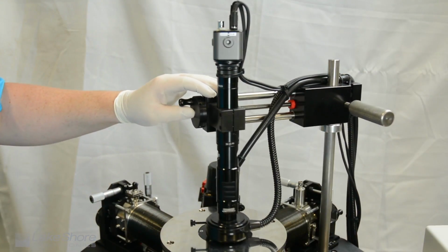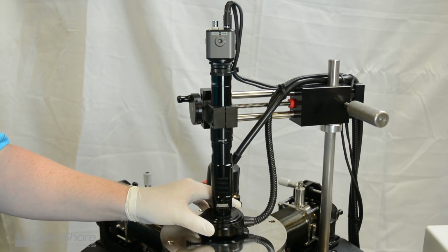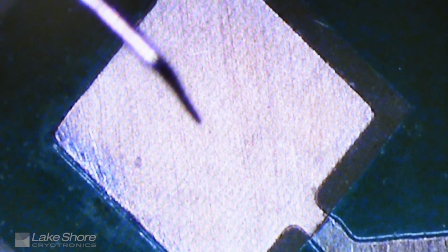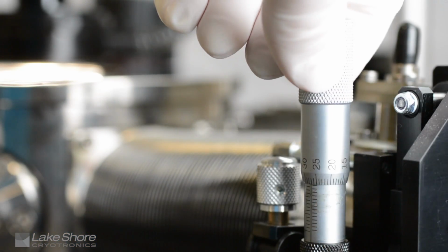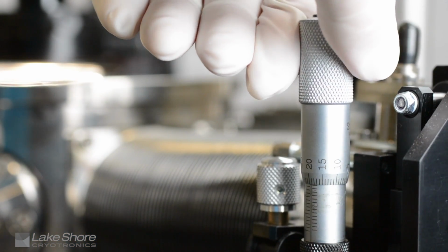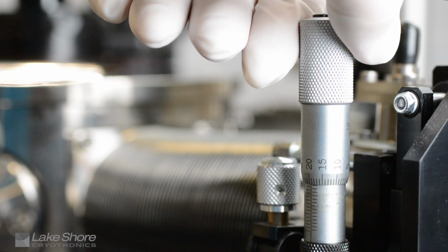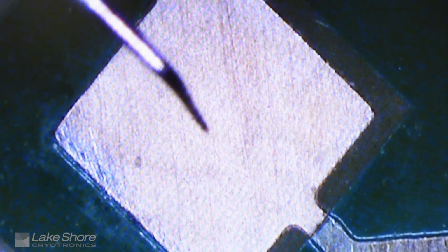Then we will swing the microscope back over the viewport and adjust the microscope to fill the monitor with the sample image and focus at the height of the sample landing pad. Use the Z-axis micrometer or Z-axis adjustment to lower the probe tip until the tip begins to come into focus. When the tip begins to come into focus, begin to slow the downward adjustment inputs.